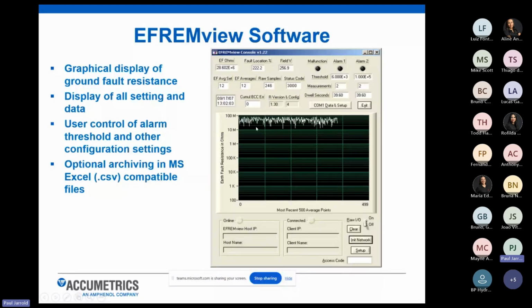Over time, as that resistance value starts to drop and gets below about 500 kiloohms in value, this graph will become more of a linear chart, and you'll see a linear trend line of that resistance dropping. And then once it drops below the 100K threshold, it'll send you the warning alarm, and will allow you to more closely monitor your equipment. And then as it drops further and gets below the 2 kiloohm threshold, it'll send the ground fault warning alarm.